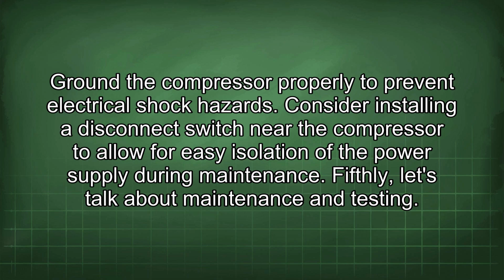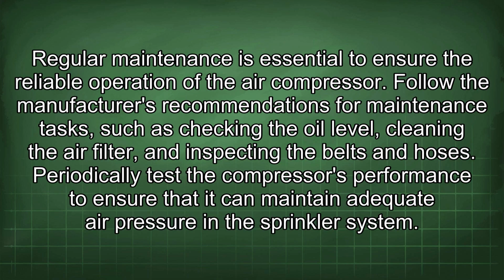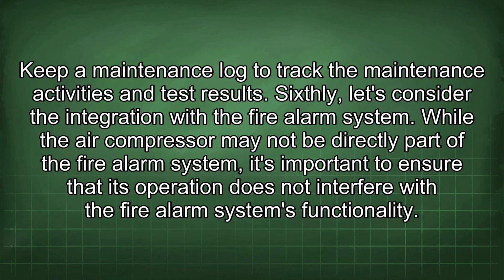Fifthly, let's talk about maintenance and testing. Regular maintenance is essential to ensure the reliable operation of the air compressor. Follow the manufacturer's recommendations for maintenance tasks, such as checking the oil level, cleaning the air filter, and inspecting the belts and hoses. Periodically test the compressor's performance to ensure that it can maintain adequate air pressure in the sprinkler system. Keep a maintenance log to track the maintenance activities and test results.